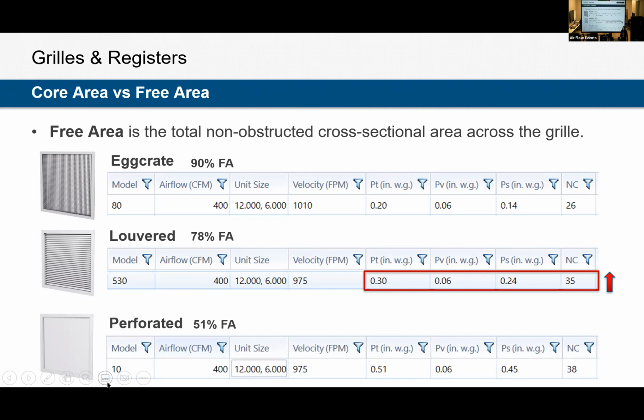I'll check on that. Isn't it the profile of the egg crate versus the louvered? So egg crate has blockages, if you will, vanes in both directions, whereas louvered will only have them in the one. So your velocity profile should be a little more or a little less turbulent probably in the louvered one. So maybe that's why velocity goes down. Well, velocity should just be flow versus area. But it's not that important.